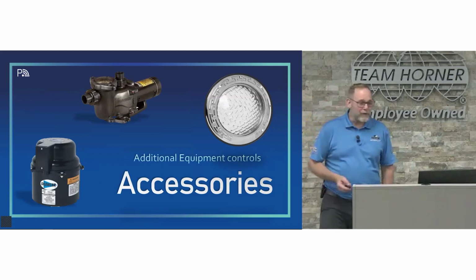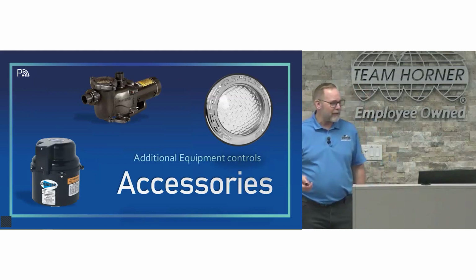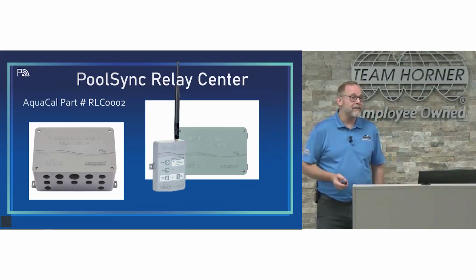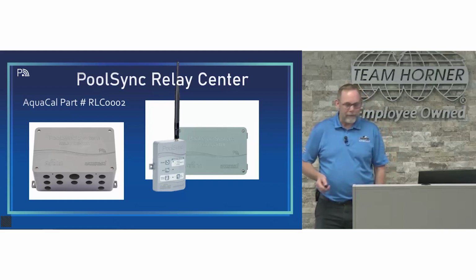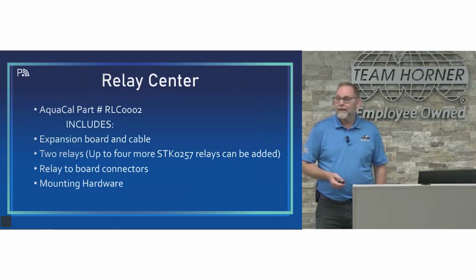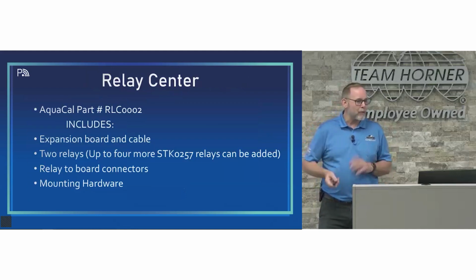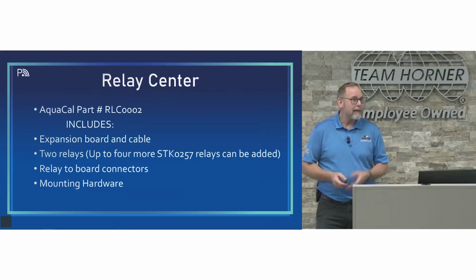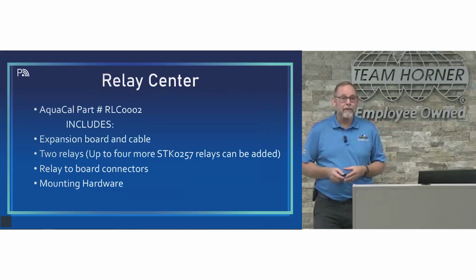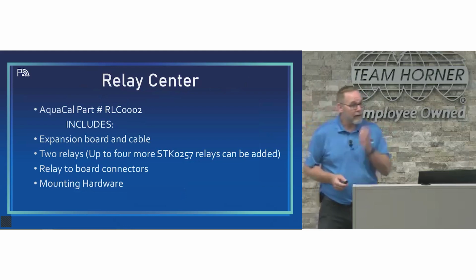So we can also control basically any pool related accessories with the addition of our relay center. The variable speed pump control, once again, you don't have to buy any equipment. You connect it right up to the heat pump control board. It works with or without the PoolSync, so you can do it directly from the heat pump control panel. But if we want to control single speed pumps, any relay controlled devices, actuators, then we need the RLC0002 relay center. The relay center comes with an expansion board and a cable that tie it into the main heat pump board. It comes with 2 relays, but there is room to mount up to 6 relays.